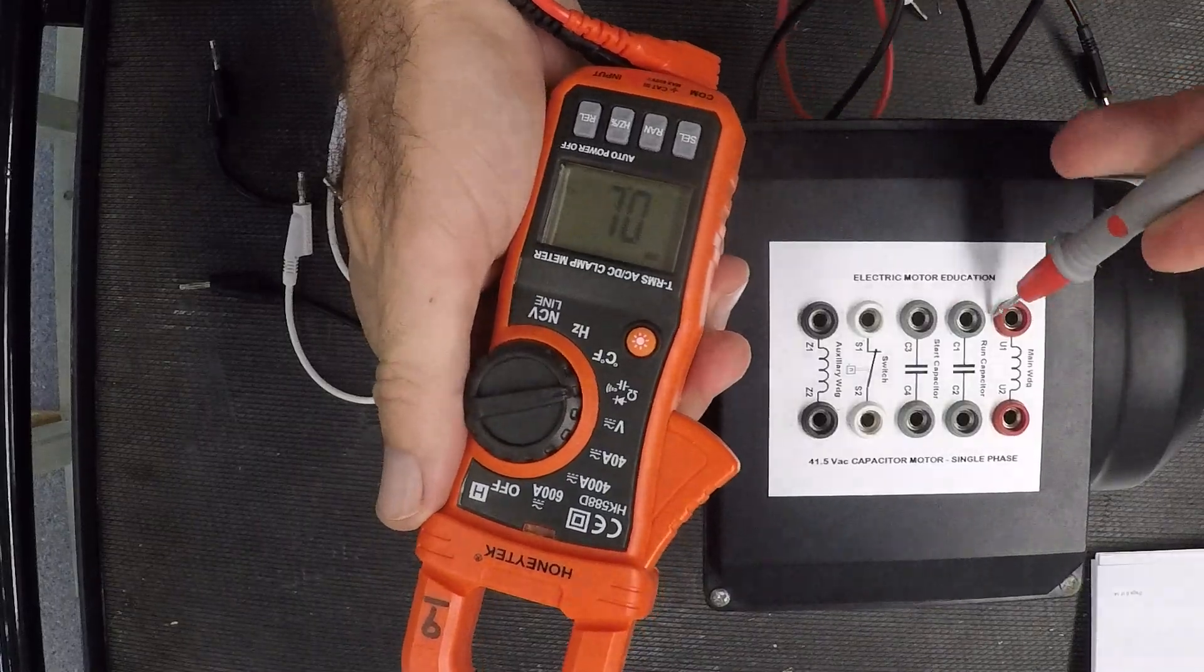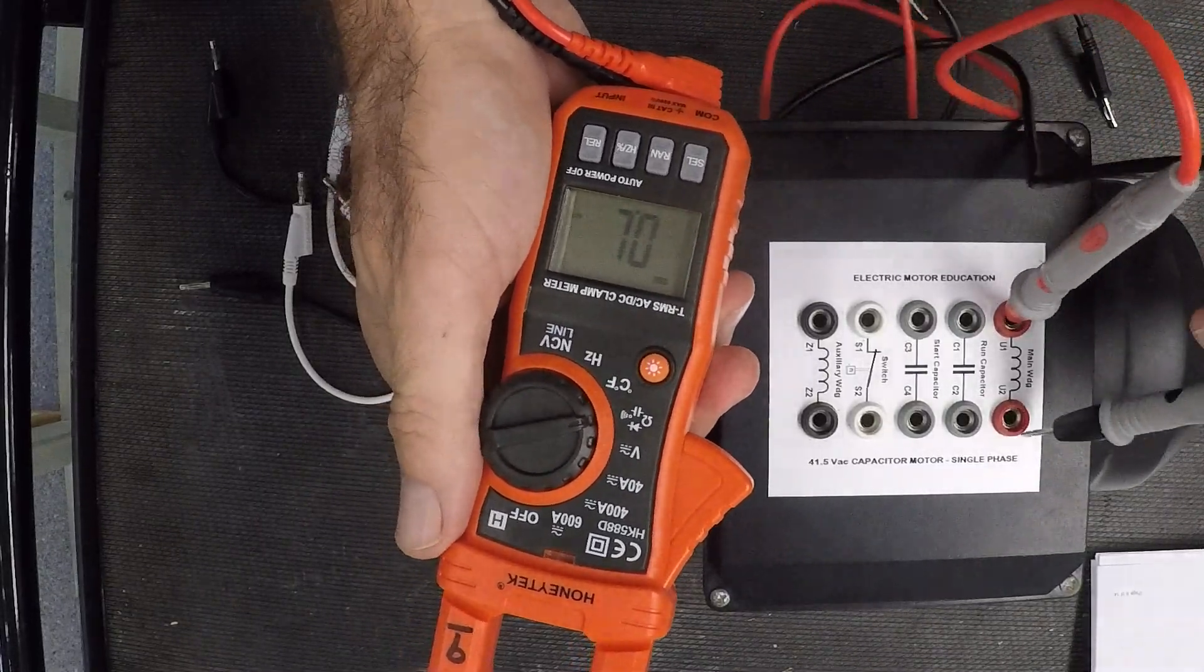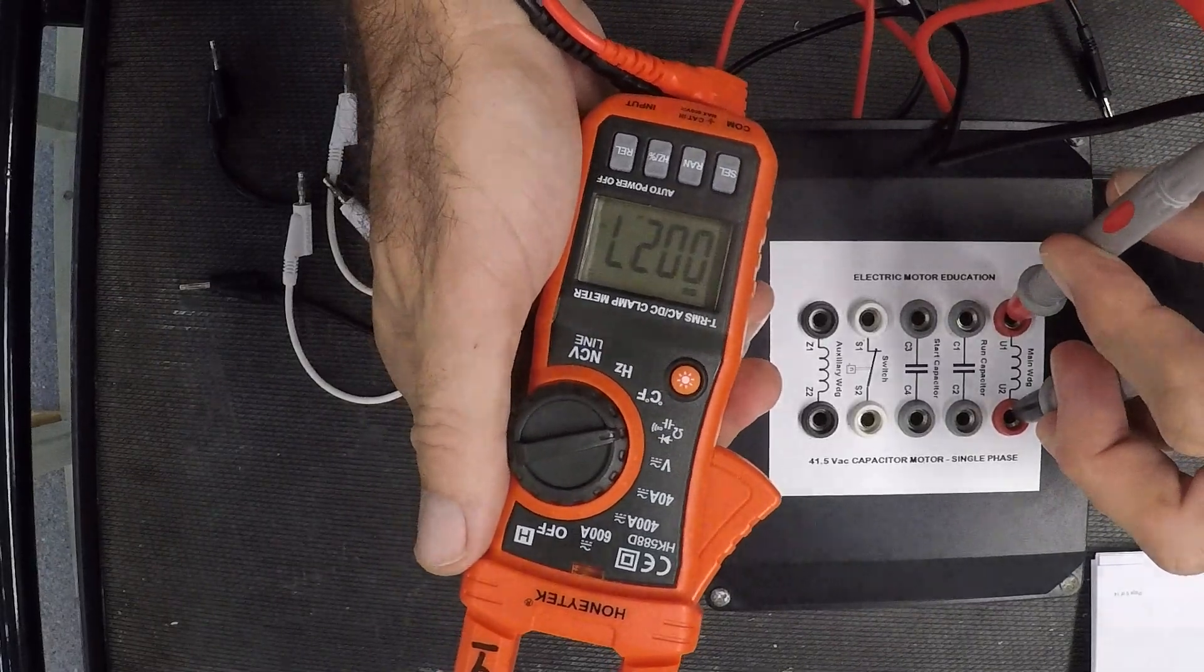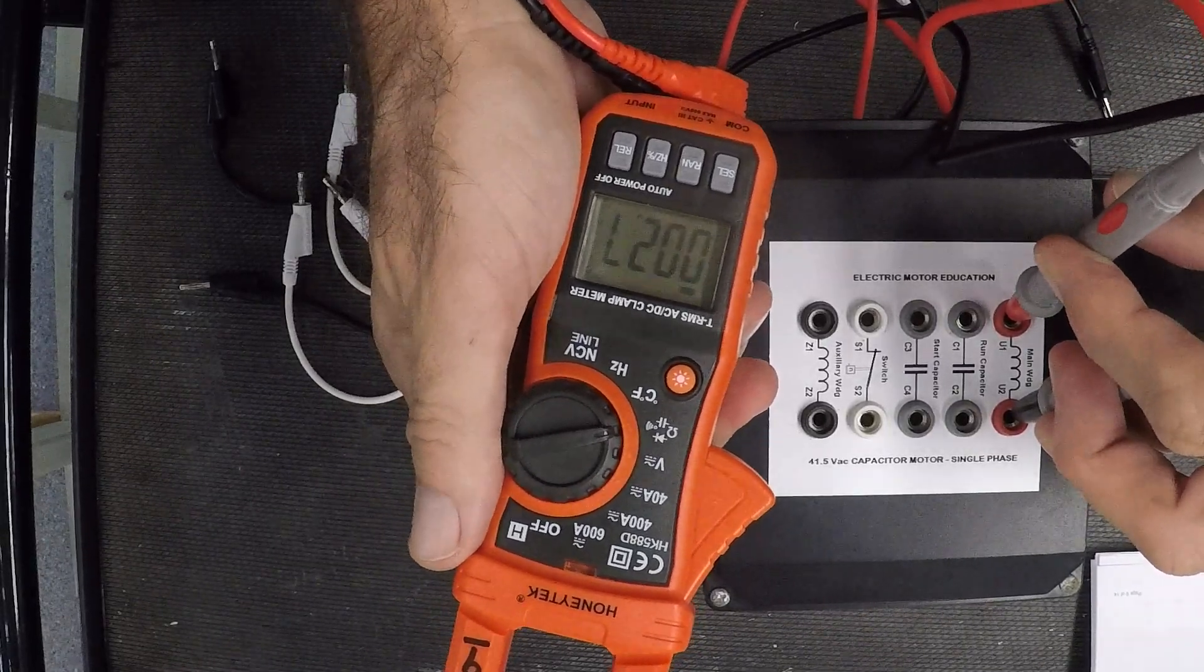First things first, I want to check my run winding. Let's see what the reading is there. I'm getting 2.7 ohms, which is good.